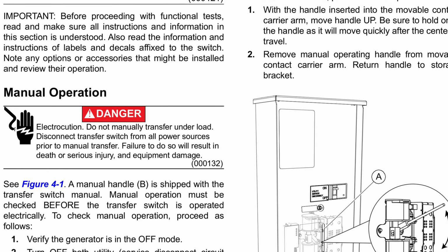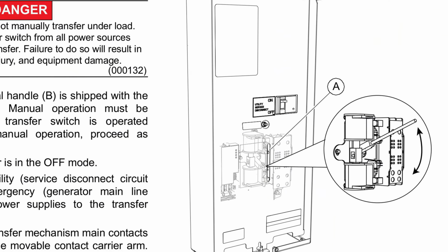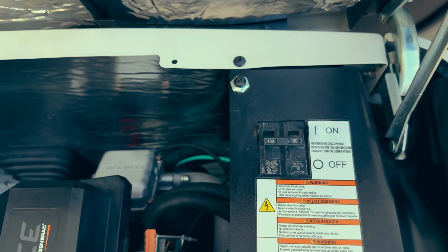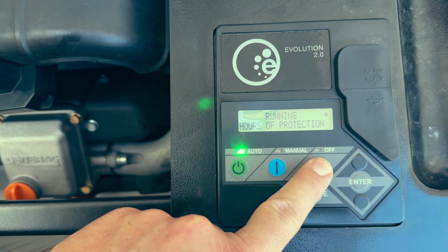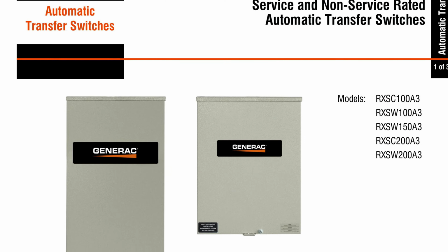Since the ATS isn't doing its job, we need to manually cut power before making the switch. Flip the generator's main breaker off and then press off on the controller. Let the generator come to a complete stop before moving on. Now we're heading to the transfer switch.